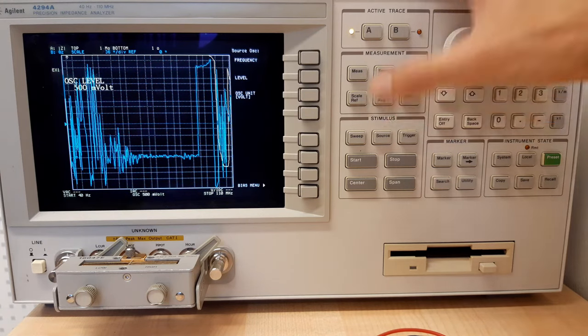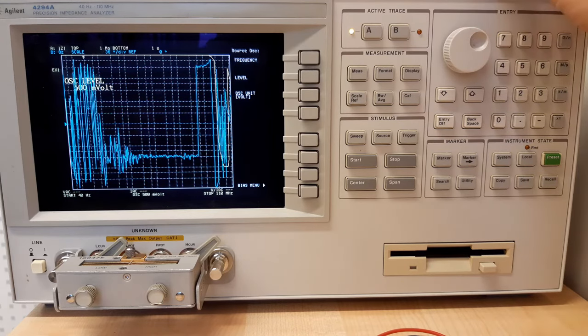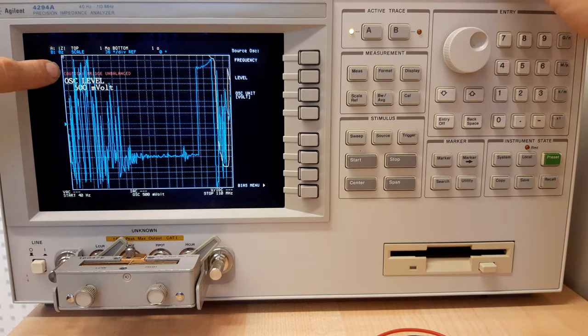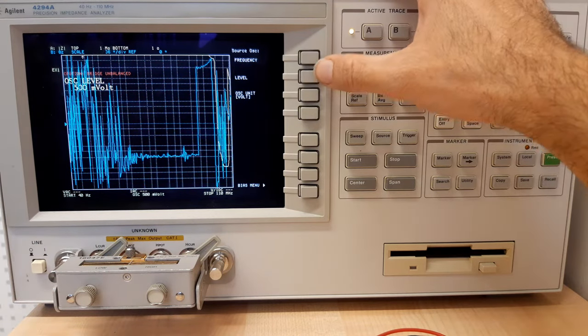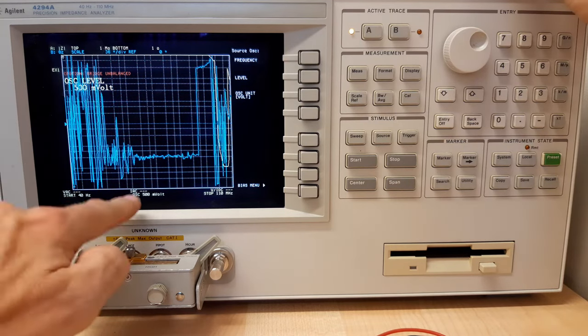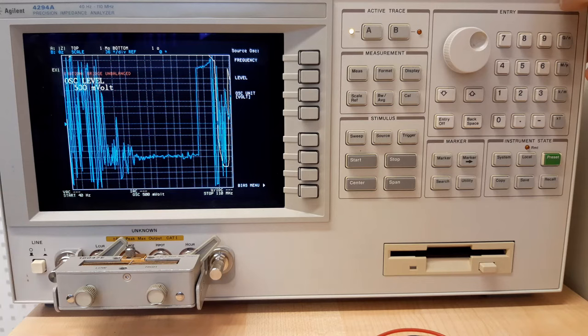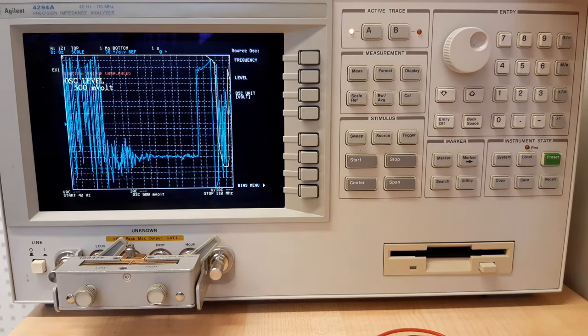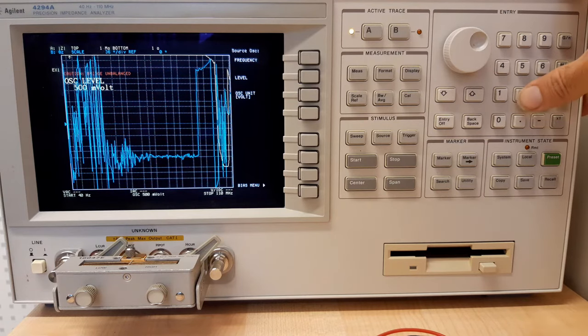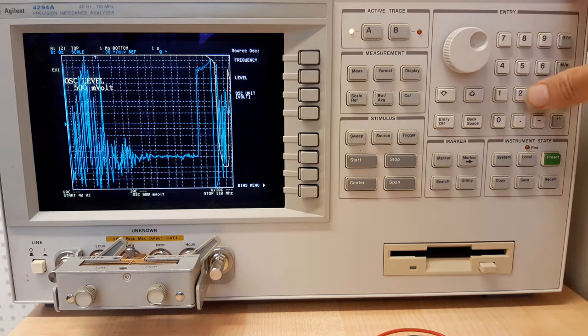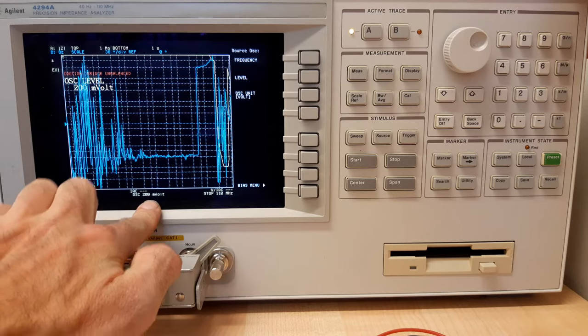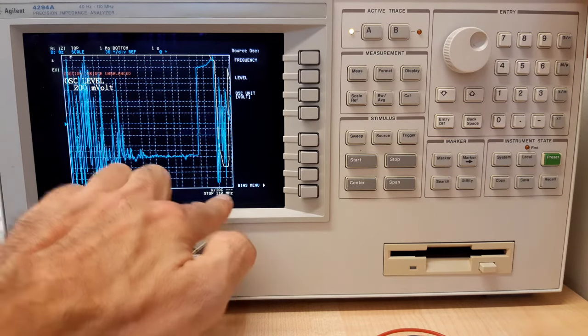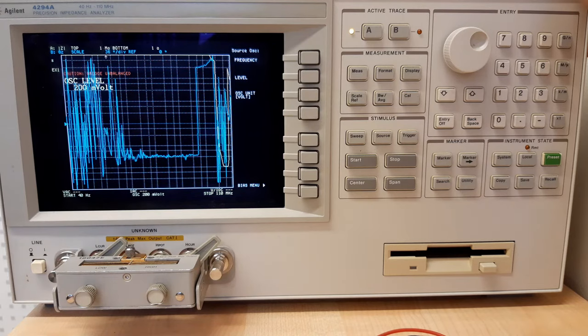The next button sets the source voltage. You may see a red warning message saying 'caution, the bridge is unbalanced' because the default 500 millivolts is quite high when nothing is connected. We'll set the level down to 200 millivolts. So now we have 200 millivolts sweeping logarithmically from 40 Hz up to 110 MHz.